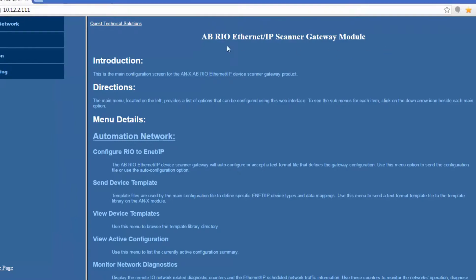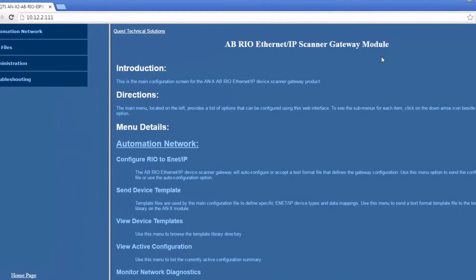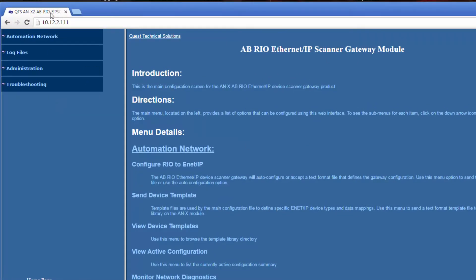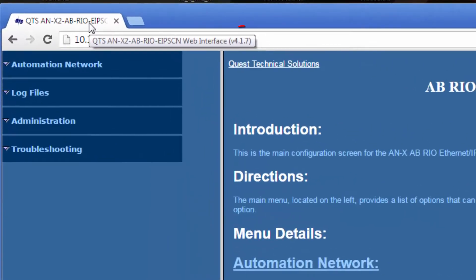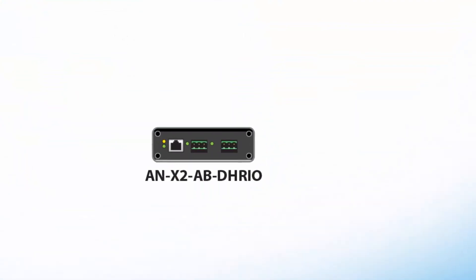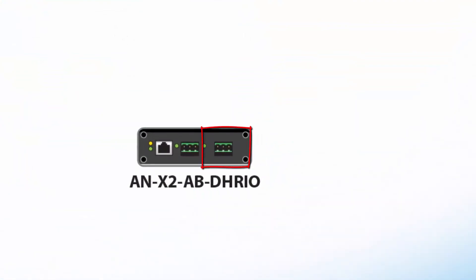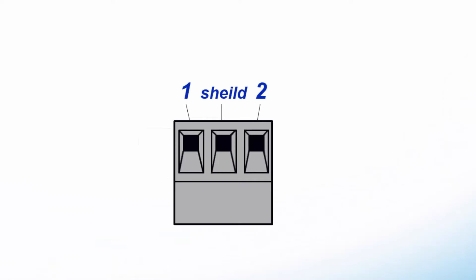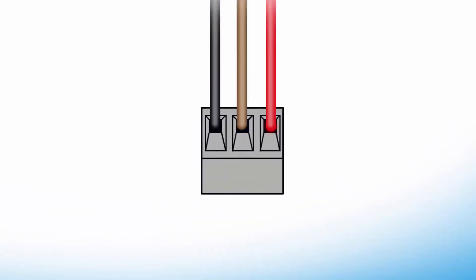If you need to find out the firmware version that you're using, you can just hold your mouse cursor over the browser tab with the ANX2 web page, and the version number will be displayed as part of the name for that web page. Finally, if you find you're unable to establish communication with the ANX2 module, you should try swapping the positive and negative wires on the communication line, as different vendors have them positioned differently.